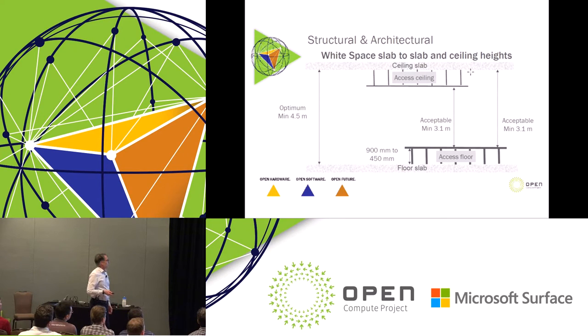Another subsystem that we've considered is the structural and architectural aspects of the white space. Within the checklist we've also given some guidance around what we think would be an optimum arrangement, not an absolute must-have for it to work. If the facility allowed for it, then a 4.5 meter slab-to-slab height would be an optimum clearance to have, but it would still work at 3.1 meters.